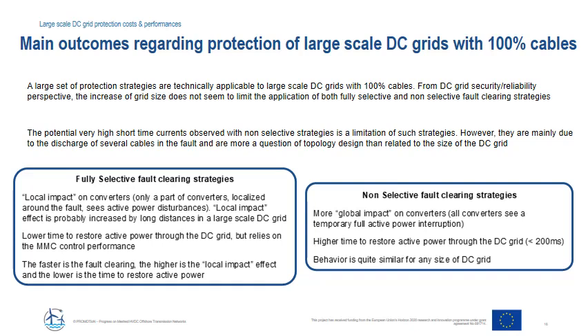Fully selective fault clearing strategies lead to a potentially lower impact on the AC system, illustrated by the shorter times needed to restore active power through the DC grid that relies on the MMC control performance, and by a local impact on converters. Only a part of the converters experiences a significant temporary power flow disturbance. The local impact effect is probably increased by long distances in a large-scale DC grid. The faster the fault clearing, the higher the local impact effects, and the lower the time needed to restore active power.